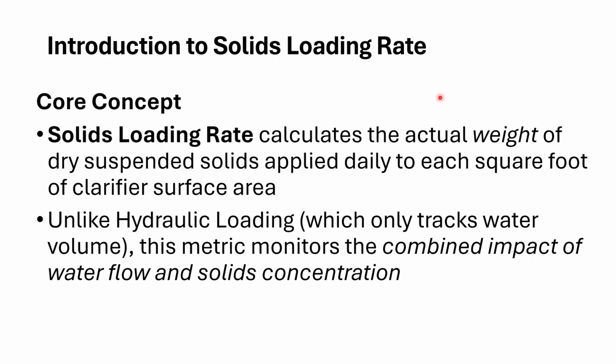So let's look at solids loading rate now. This is the third metric we mentioned. Solids loading rate is going to calculate the actual weight of dry suspended solids applied daily to each square foot of the surface area of that clarifier. It's not hydraulic loading. In hydraulic loading, we're looking at only the water or wastewater volume.